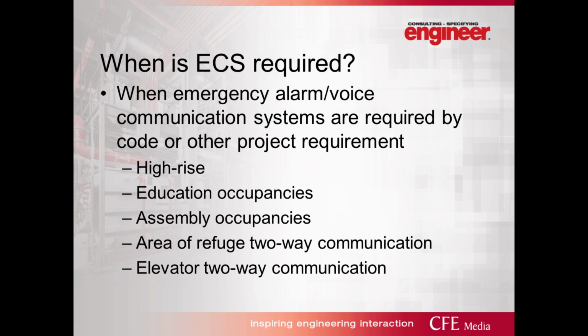Now, we talked a little bit about emergency communication, voice, and when it's driven by occupancies. There's a couple of systems that I did want to mention. We have what we call area of refuge two-way communication that is required by the building codes and NFPA 101. Now, this can be very confusing because in a sprinkled building, there typically is not a requirement for an enclosed room as an area of refuge. But that doesn't make the requirement for an area of refuge two-way communication go away. In that case, the two-way communication is required from the elevator lobby to a constantly attended location, or it has to communicate to an off-site location.